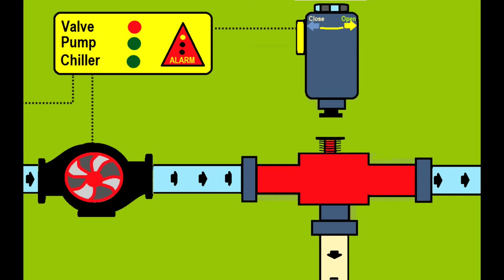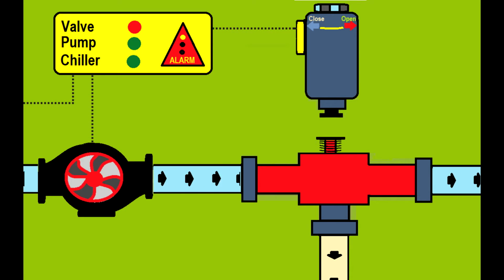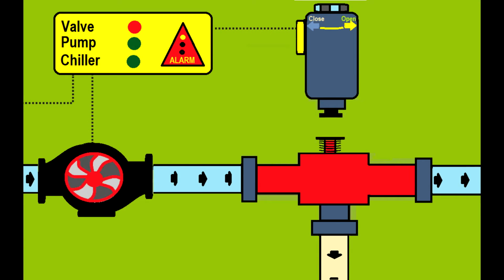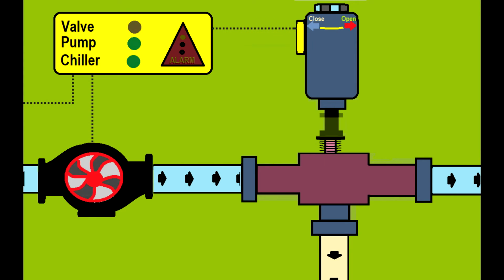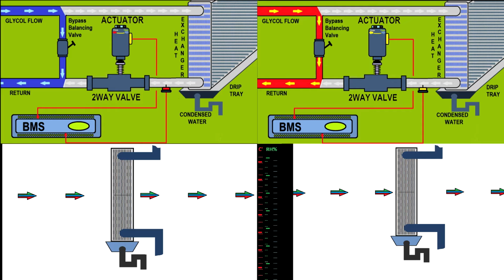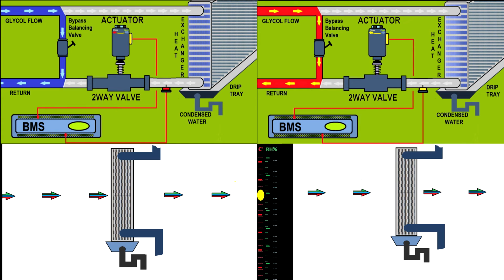Now this is again a faulty valve. The spring doesn't push the shaft to follow the actuator. This is a proportional control actuator, and the fault is quite complicated because it runs from 0 to 100%.